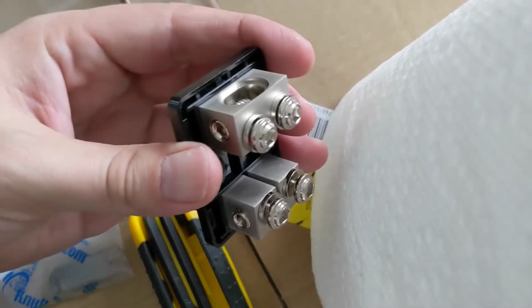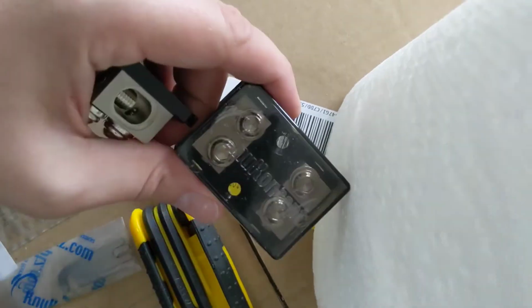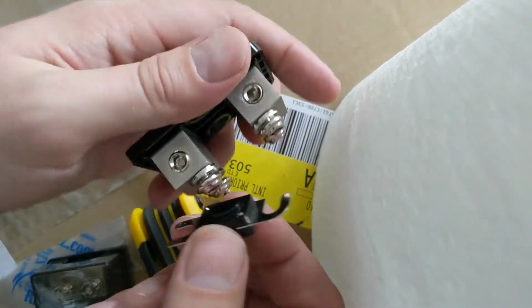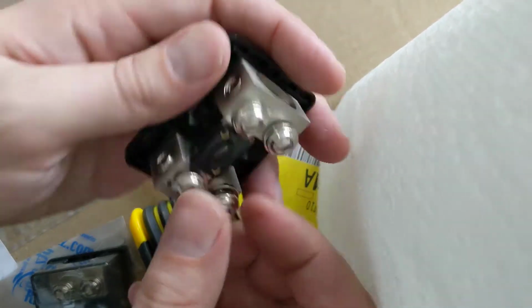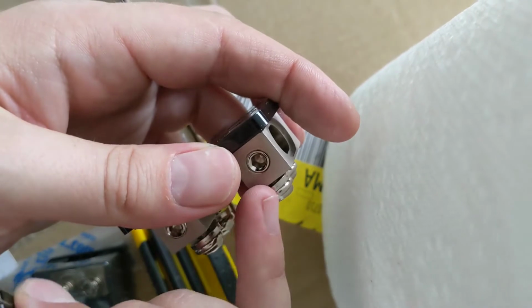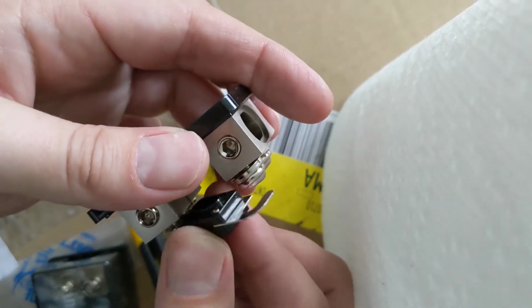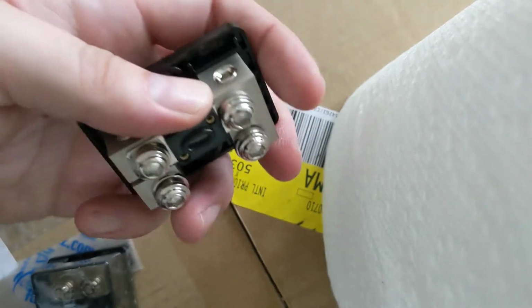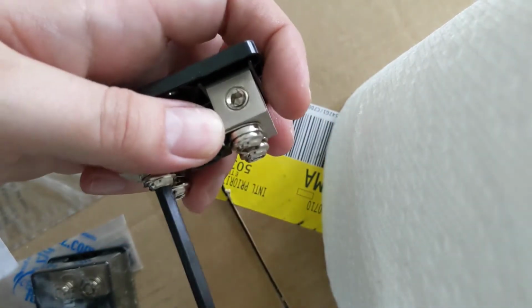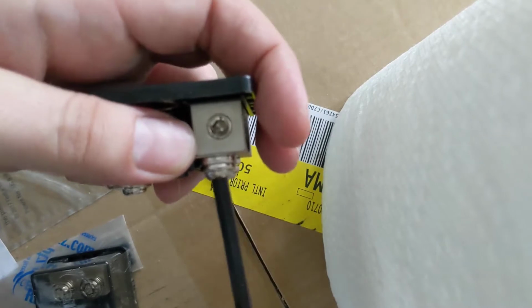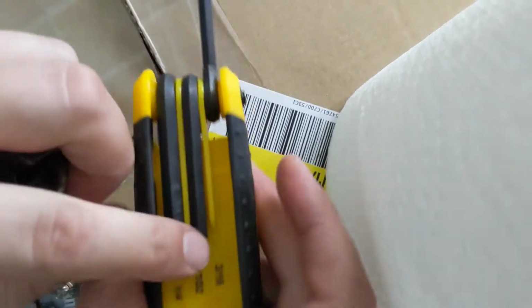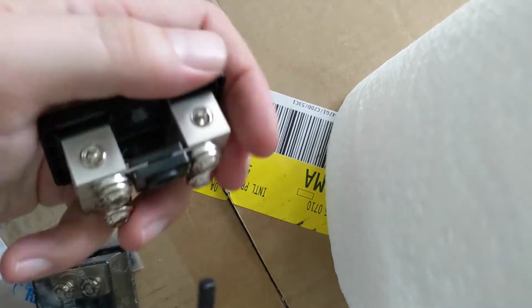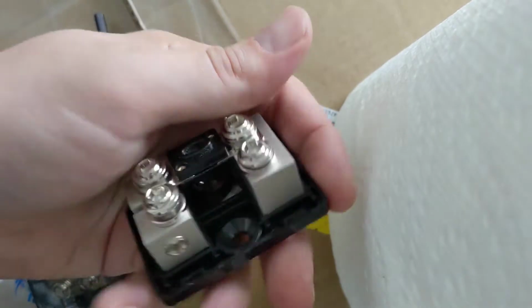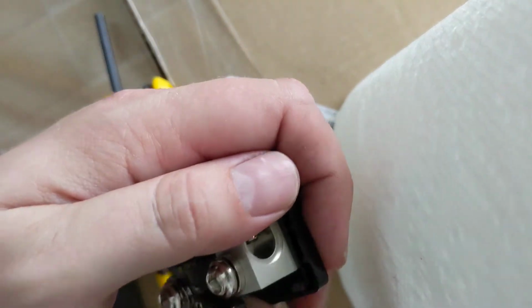Alright, so I'm just going to build up my distribution blocks here with a cover on it. This one is on the power side, so I've got a fuse for each of these locations. I'm putting it in behind the washer, between the block and the washer. I don't know if there's another way to do it that would be better. For me, I'm just interested in the most contact surface possible. I'm using a 3/16 Allen wrench. It's a little loose, so in reality these might be 5mm metric bolts. I'm not real sure, but 3/16 seems to handle it. I'm not torquing it excessively.